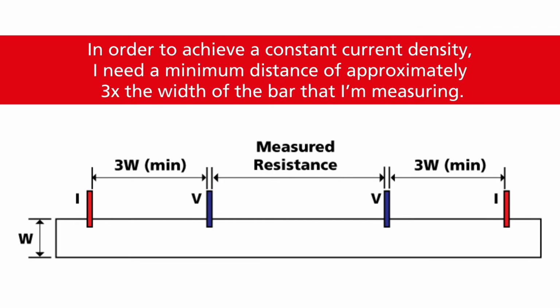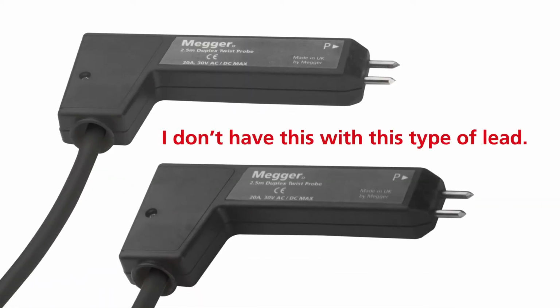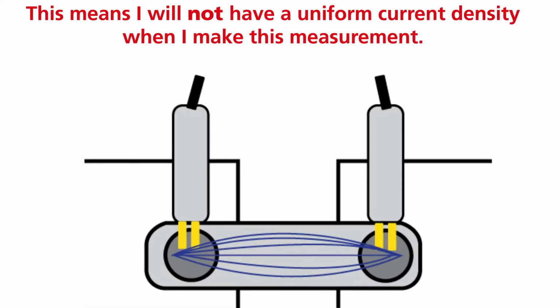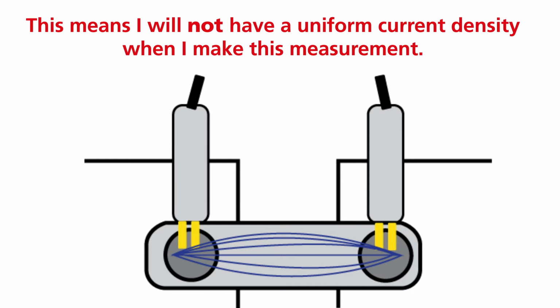The problem with this type of measurement is the distance between the pins. In order to achieve a constant current density, I need a minimum distance of approximately 3 times the width of the bar that I'm measuring. I do not have this with this type of lead. This means I will not have a uniform current density when I make this measurement.